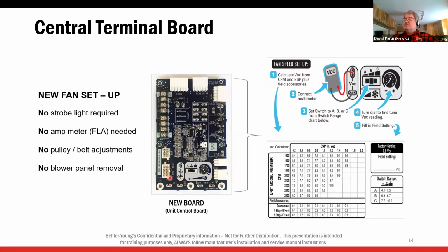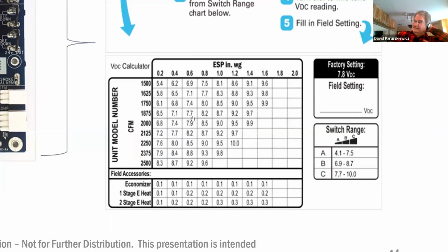So the new central terminal board, like I said, is for setting up our static pressure. Now, it's kind of frightening sometimes when you get out to a job site and guys are having blower problems, and we say, "Did you set the static?" Well, whatever the factory set it at. That's not a good answer. That doesn't work. The factory doesn't know what your ductwork is, so we have to set this up in the field. And if you're not setting them up, you're going to go back and you're going to have problems. The smarter the equipment gets, the more particular it is.